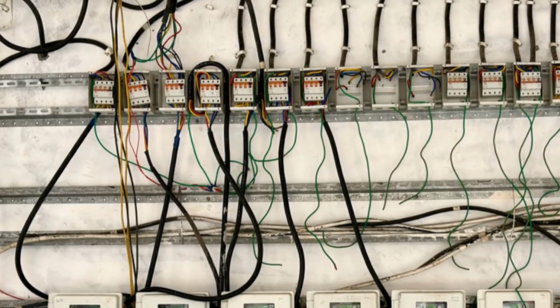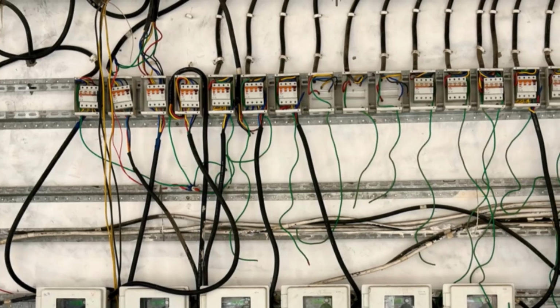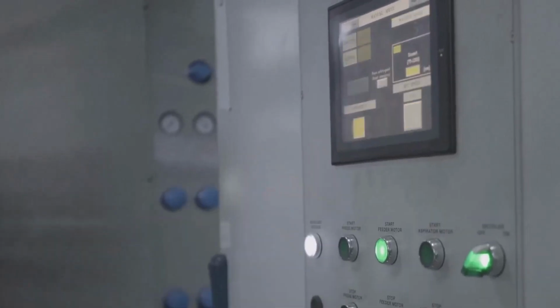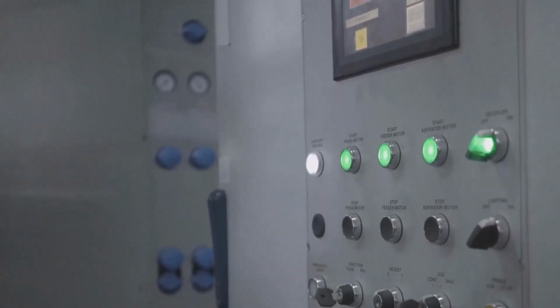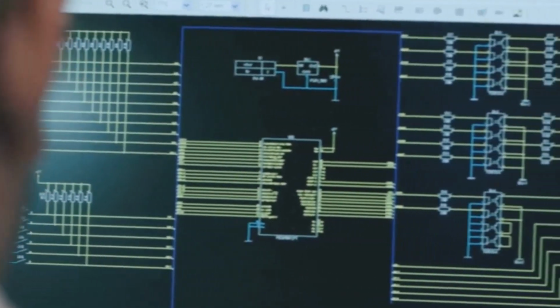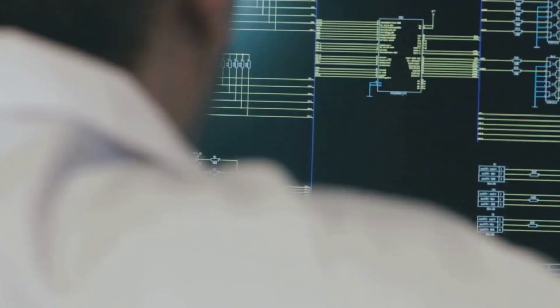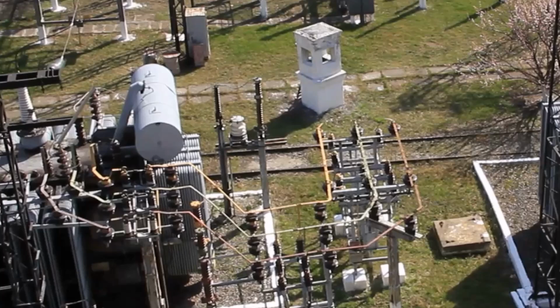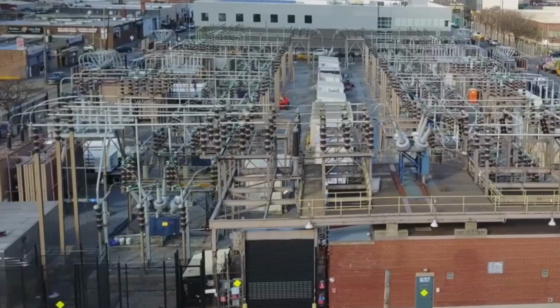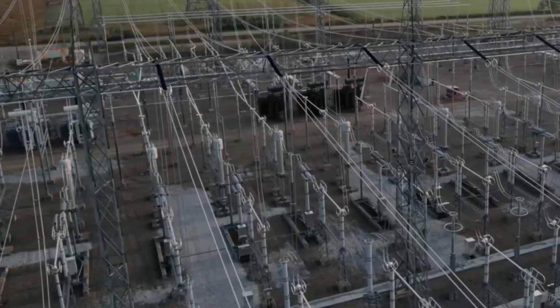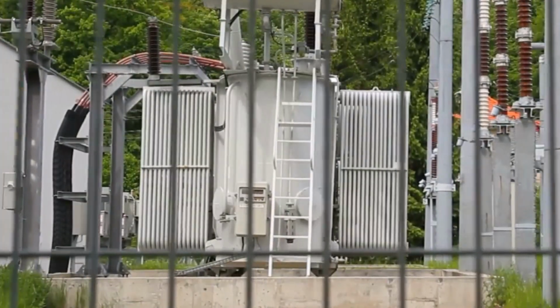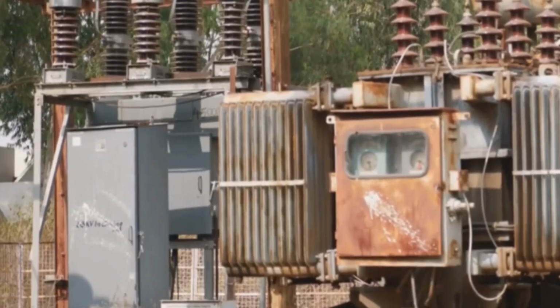So, how do we calculate the total power in a balanced Y system? Power is the rate at which electrical energy is used, and we can figure it out using a straightforward formula. The total three-phase power is equal to the square root of 3 multiplied by the line voltage multiplied by the line current. The formula looks like this. Power equals the square root of 3 times line voltage times line current. This simple equation lets us calculate the total power delivered by all 3 phases combined. It's an essential tool for engineers to ensure that transformers, generators, and wires are correctly sized for the job they need to do, preventing overloads and ensuring efficient operation.